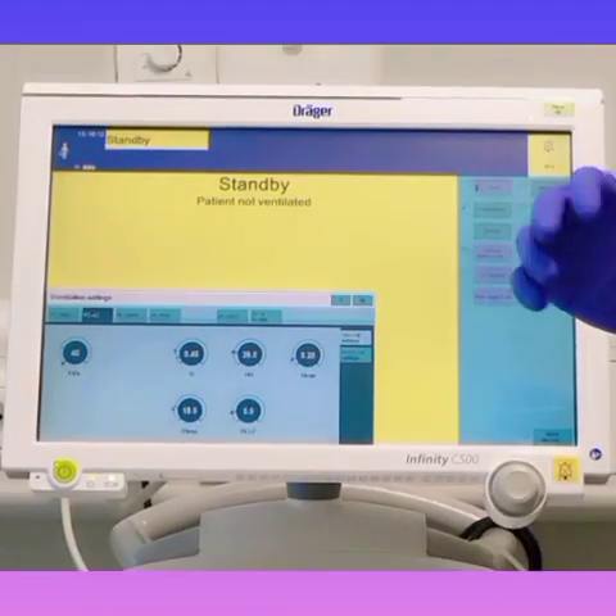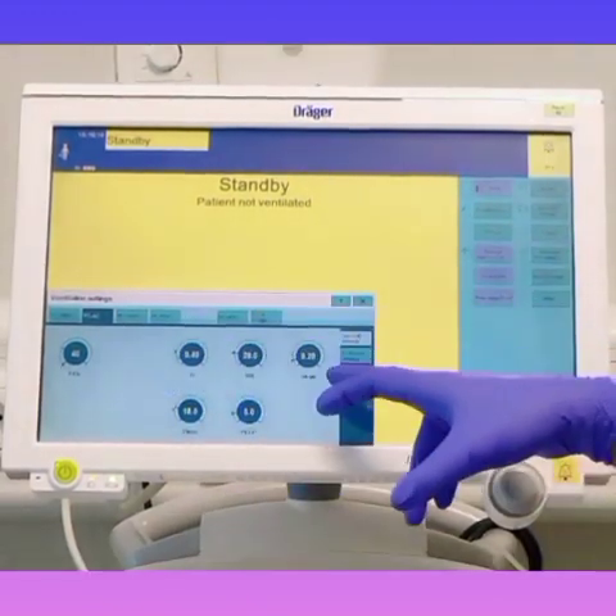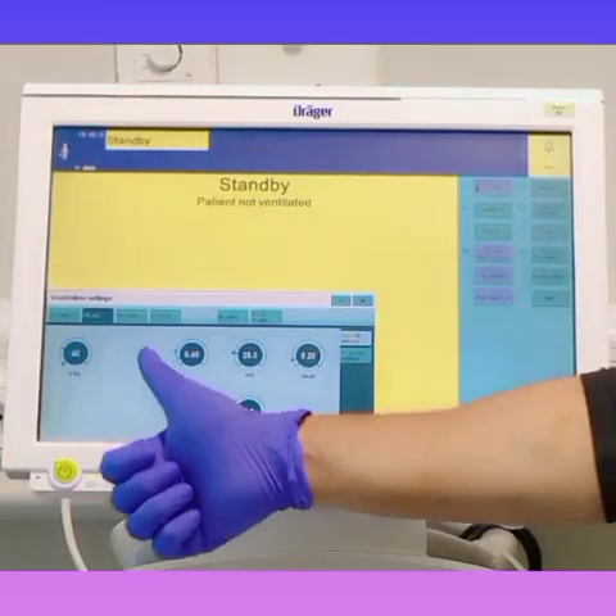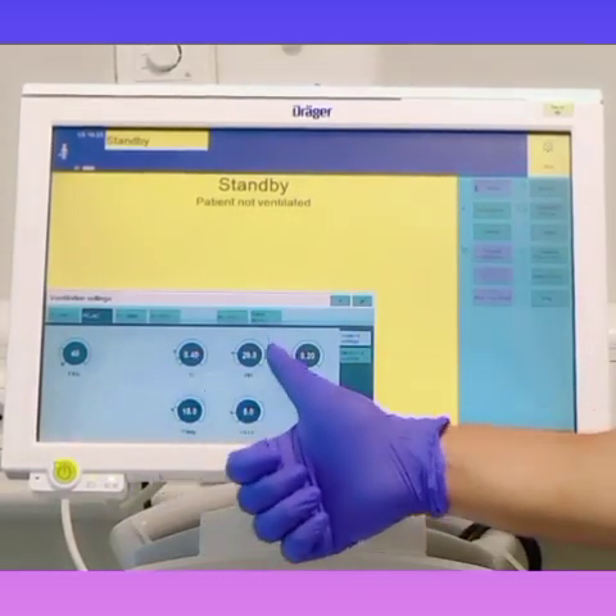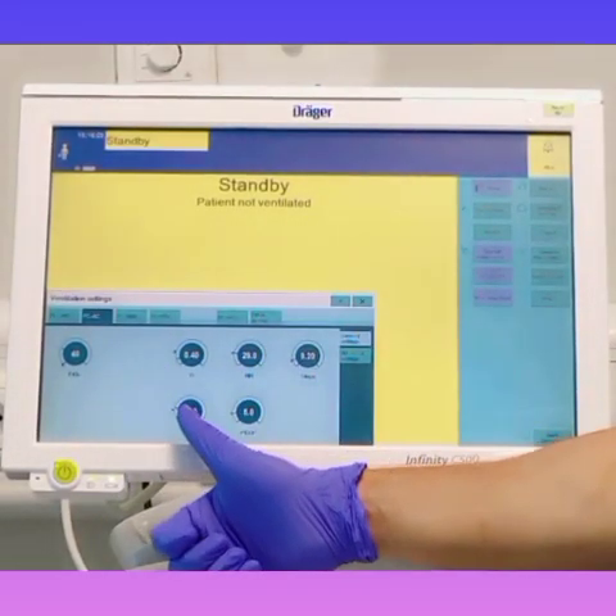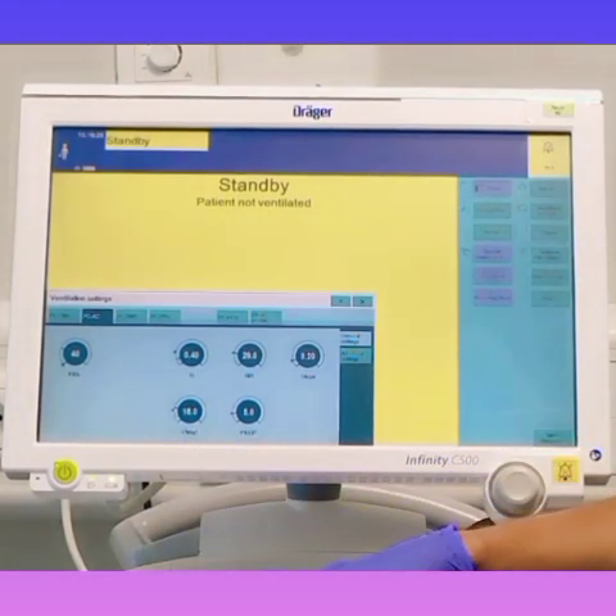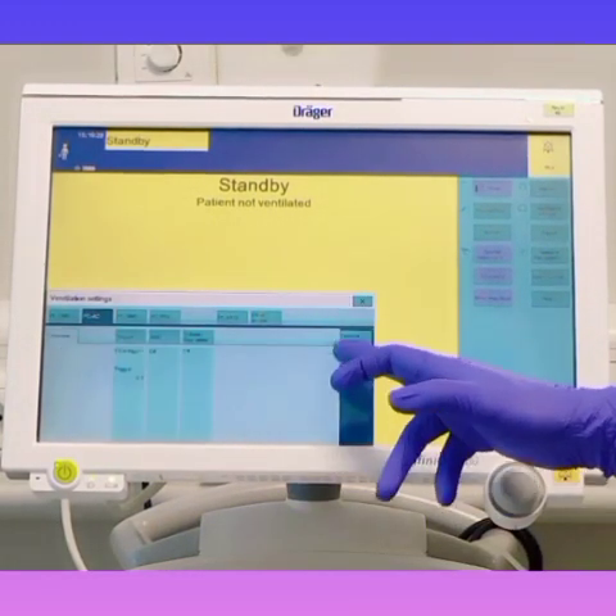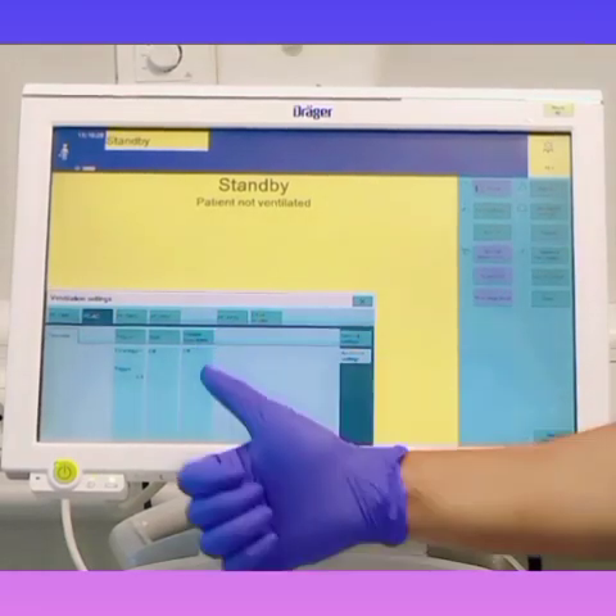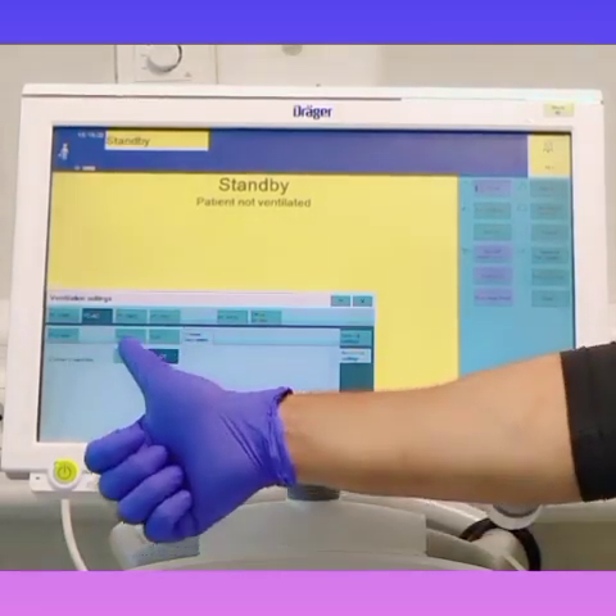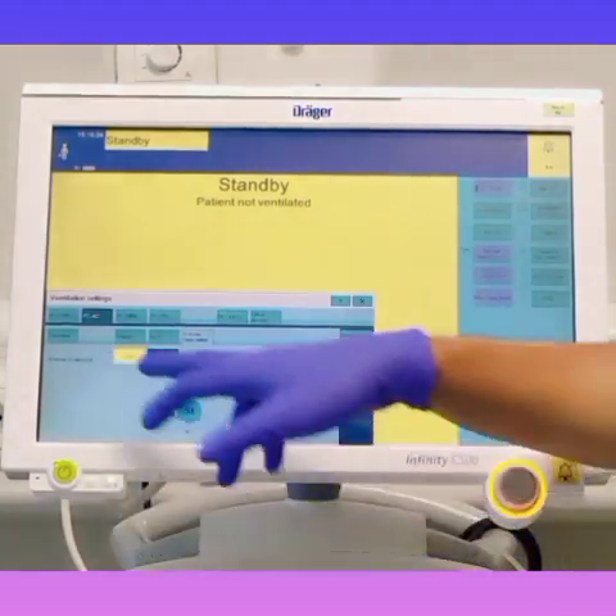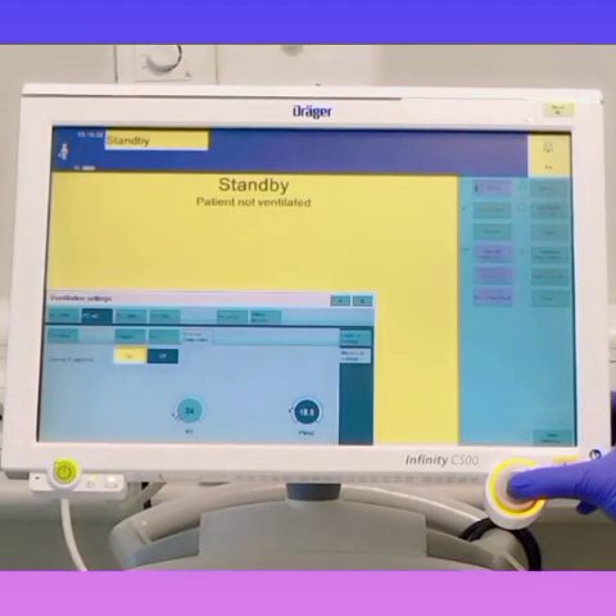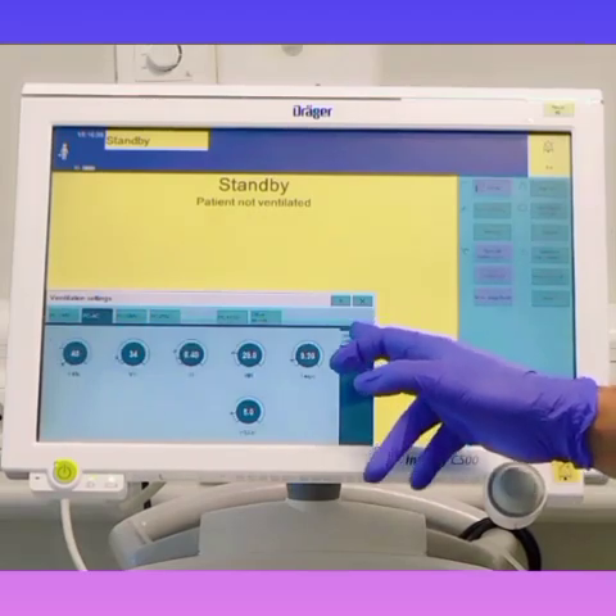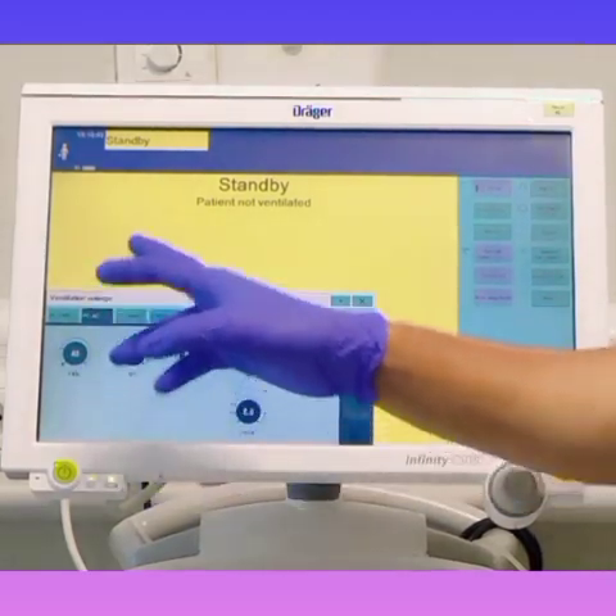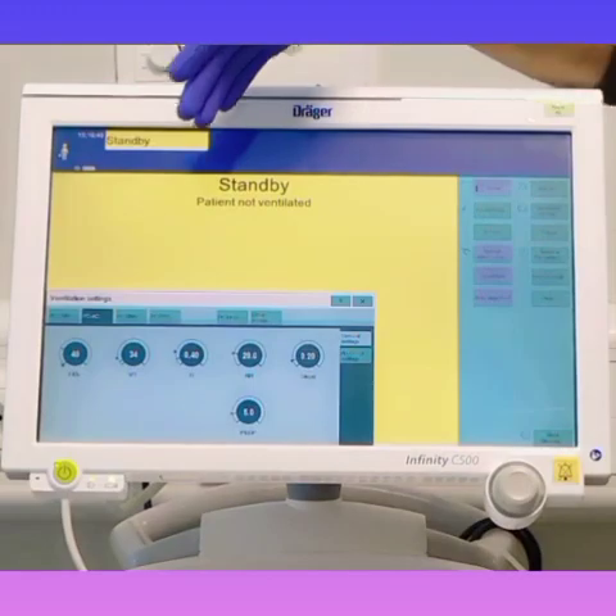For volume control, we have to first turn our tidal volume on. As you can see here, we have no tidal volume. We have inspiratory time, respiratory rate, PEEP and peak inspiratory pressure. For turning on the option of tidal volume, we have to go to the additional settings. As you can see here, volume guarantee. Press the volume guarantee. Now you can turn it on by pressing the knob. Go back to the general settings. As you can see here, we have our tidal volume here. Now this is purely your volume control mode.